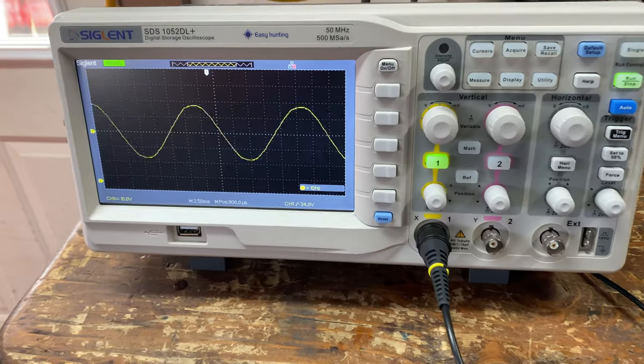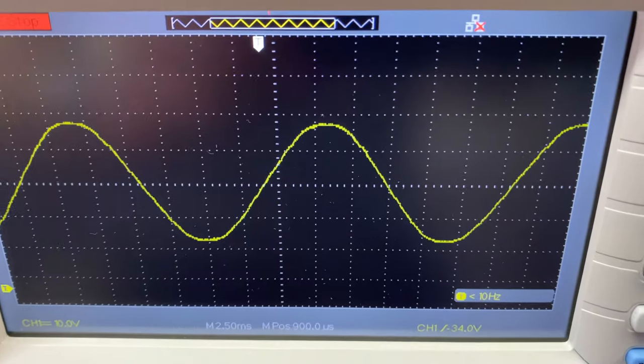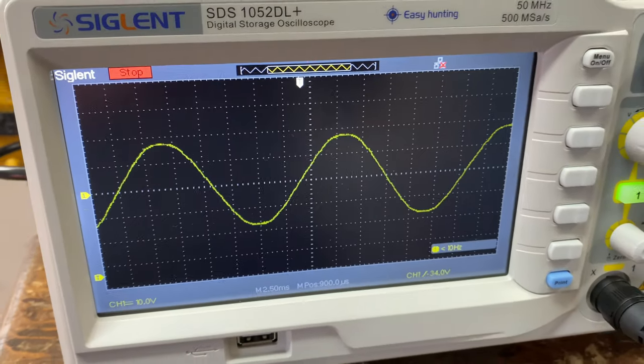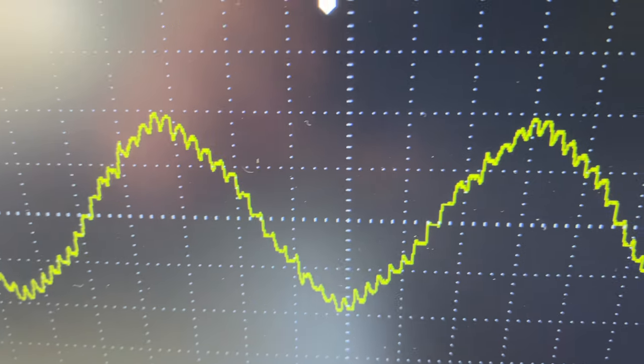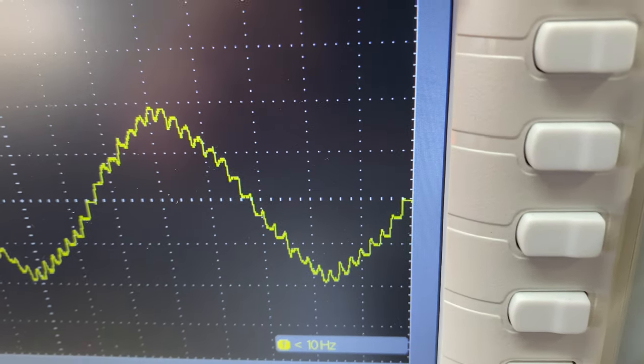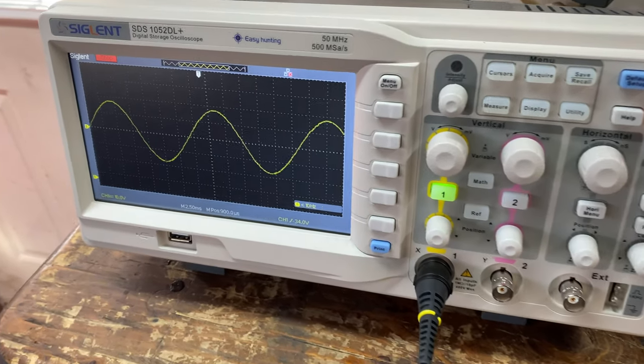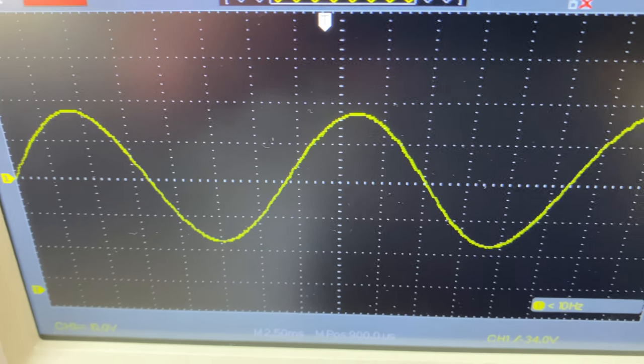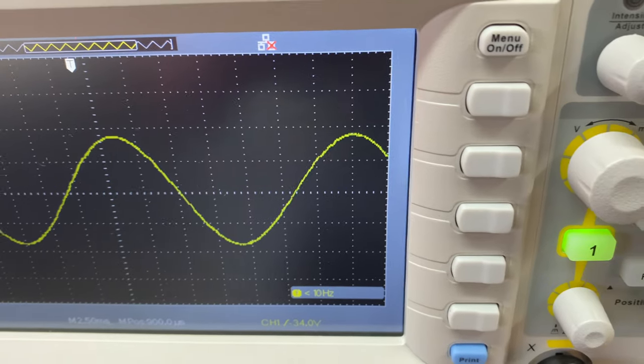Let me show you exactly what I mean. The oscilloscope you see here is connected to grid power, and you can see a nice smooth sine wave pattern — this is what's called pure power, with the smooth rising and falling of voltage. This is what alternating current, commonly known as AC power, is all about. Now take a look at the screen again — this is the output of an ordinary non-inverter generator. The deviation from the pure sine wave pattern is what can and does cause trouble with sensitive electronics, especially equipment involving audio. Now look at the waveform created by an inverter generator — it's just as pure as grid power, and even better sometimes, depending on your electrical utility. For many applications an ordinary non-inverter generator works just fine, but I have yet to see any non-inverter generator that can power sensitive electronics properly all the time, especially those items involving sound systems.